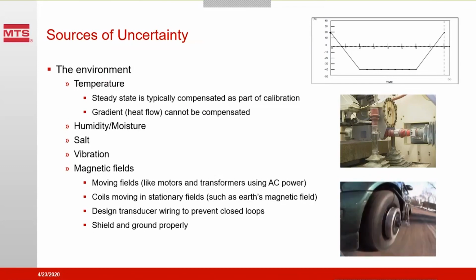But if we have, say, heat on one side of a transducer and cold on the other side, now we've got a real problem. We can't compensate for heat flow or differential temperature across the transducer, and so that is going to change our data. In such cases where we have transducers in environments that may involve temperature, we often put water cooling plates on each end of the transducer, so we try and maintain the same temperature at both ends, rather than specifically heating or cooling the transducer to a certain temperature.